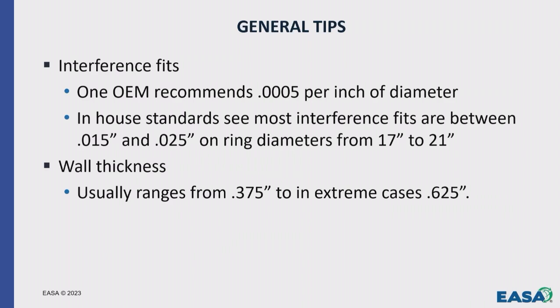Interference fits. If you have a rotor where a stainless steel ring has broken and you're wondering what to do to repair it, I put that first line in there. One OEM recommended to us 5 tenths per inch of diameter.